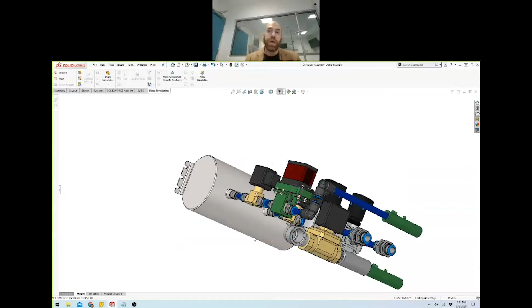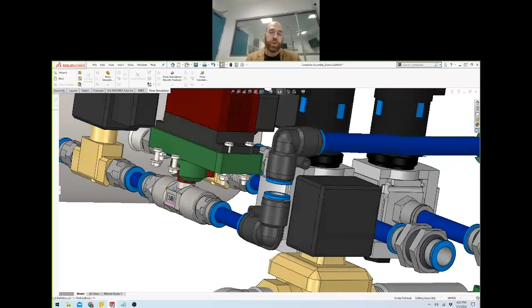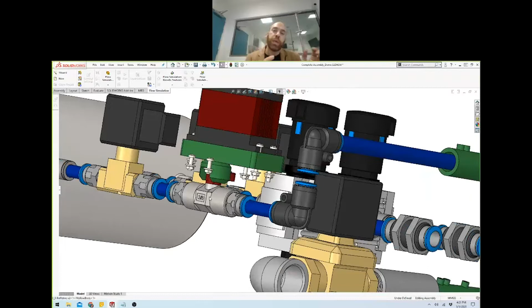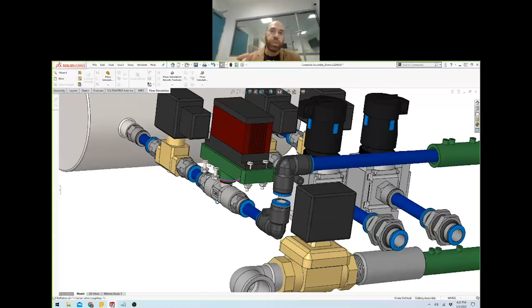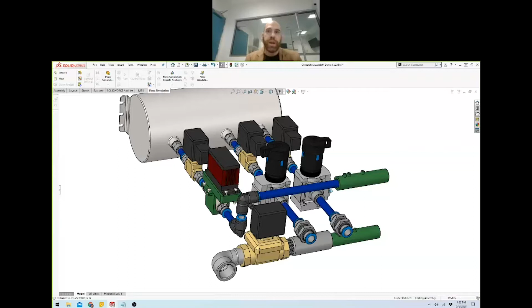Then you have something that has been required by the British government when they wrote the rapid ventilator requirements, which is the pressure regulated volume control. So typically they're trying to reach a certain pressure point at every cycle, with the target becoming, after a couple of cycles, reaching the right volume. So they try to give the right volume, which is the target of the mode, but they want to do that while going step by step with the pressure upwards and upwards and upwards. This particular mode is typically called a fire and forget mode.